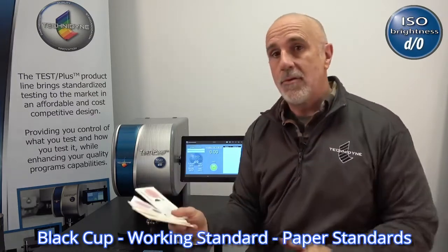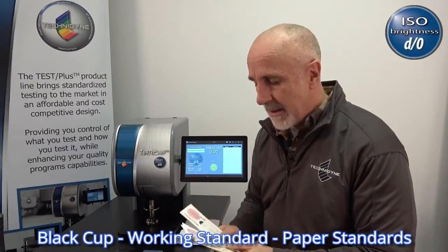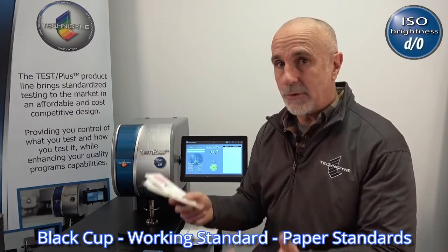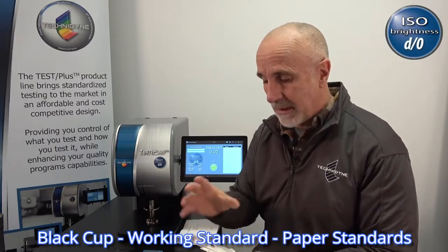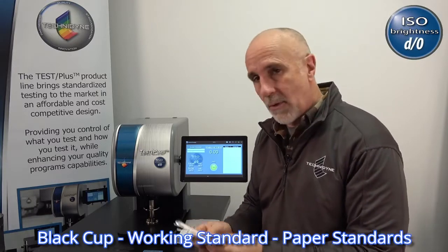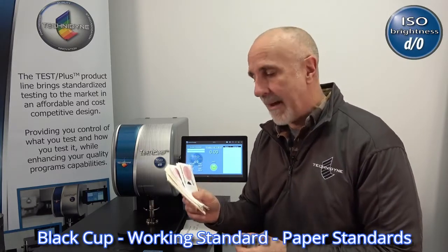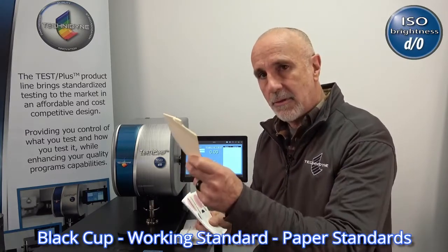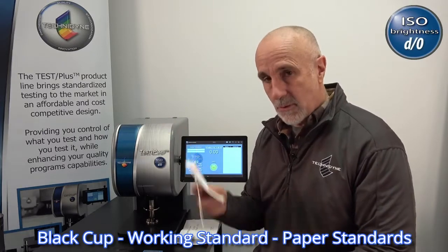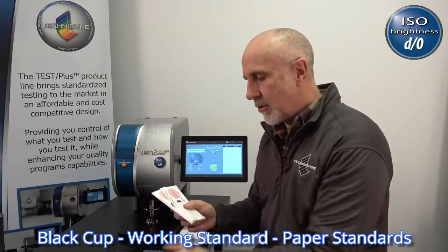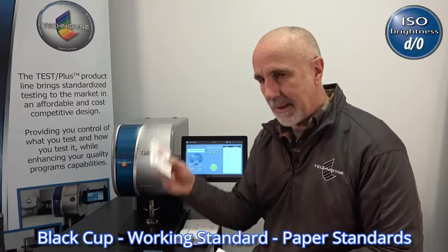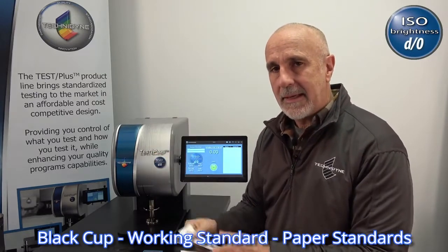We recommend you get these on a monthly basis because they are made of paper and they will degrade quickly over time, or they could get soiled. So you want to make sure you have good fresh papers for that. Within this set, you'll get two that are verification standards, a 60 and a 70 range, but the two primary calibration standards are the 90 non-fluorescent and the fluorescent standard, okay?